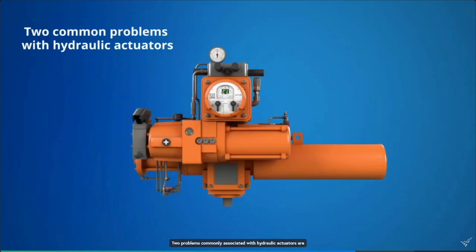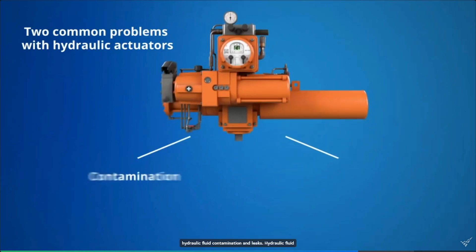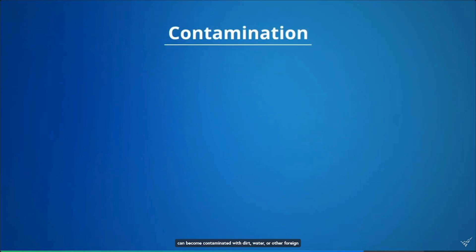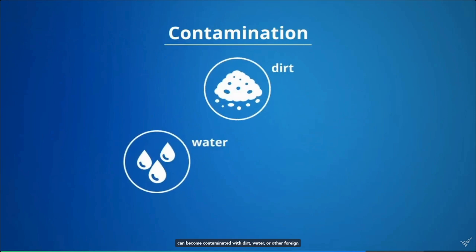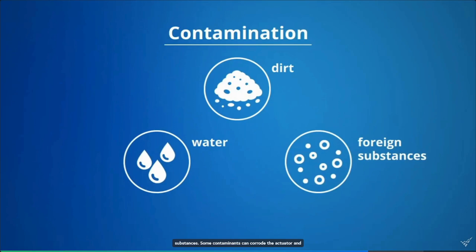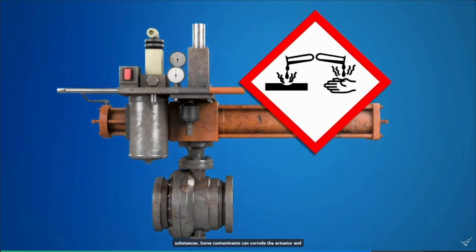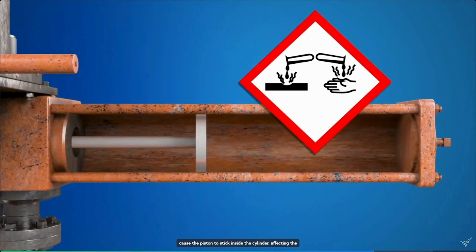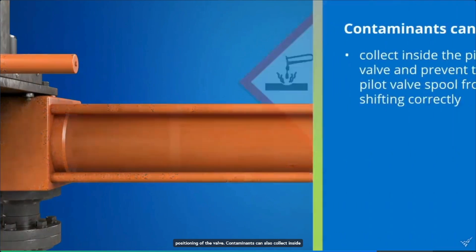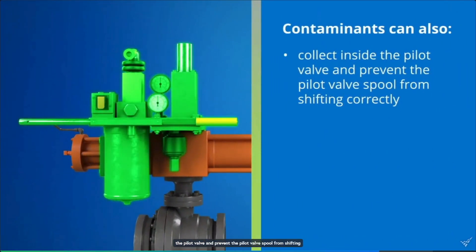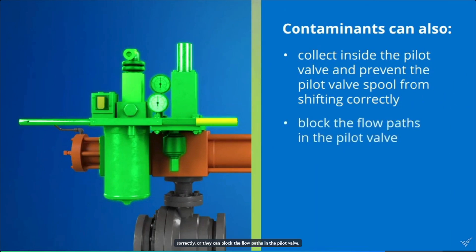Two problems commonly associated with hydraulic actuators are hydraulic fluid contamination and leaks. Hydraulic fluid can become contaminated with dirt, water, or other foreign substances. Some contaminants can corrode the actuator and cause the piston to stick inside the cylinder, affecting the positioning of the valve. Contaminants can also collect inside the pilot valve and prevent the pilot valve spool from shifting correctly, or they can block the flow paths in the pilot valve. In either case, the pilot valve would not operate correctly and the actuator would be unable to position the valve correctly.